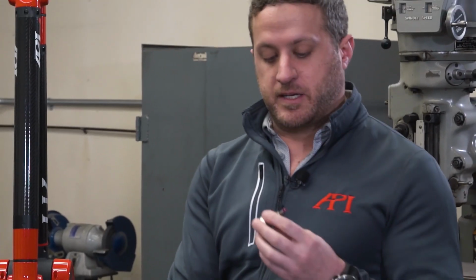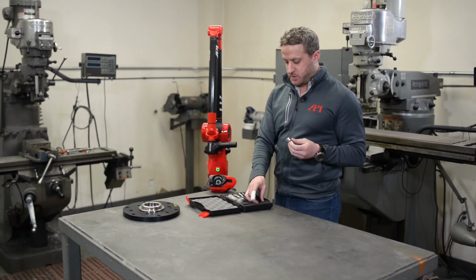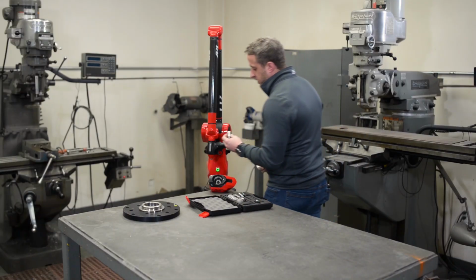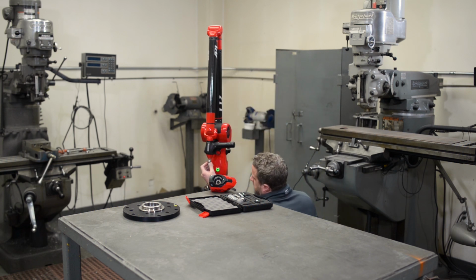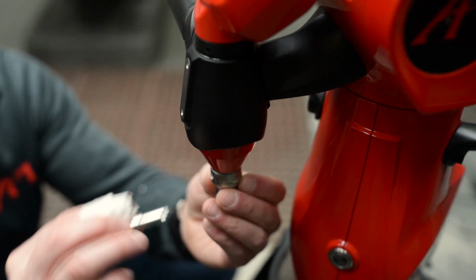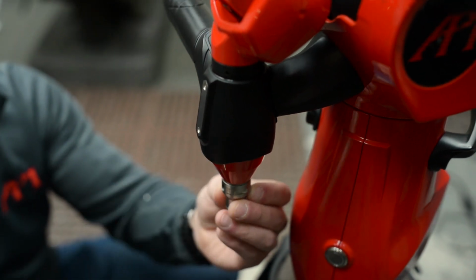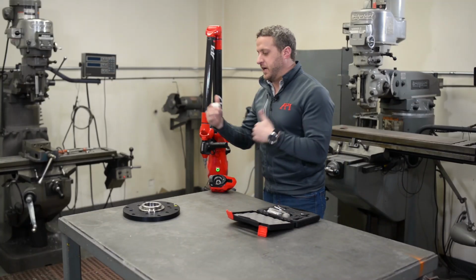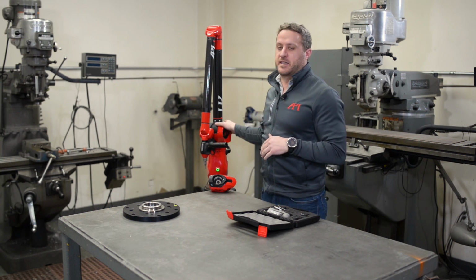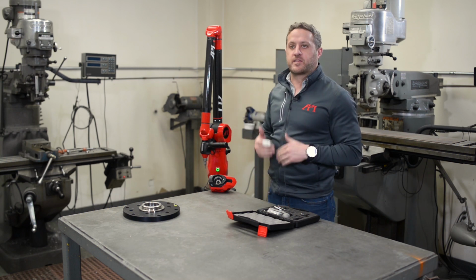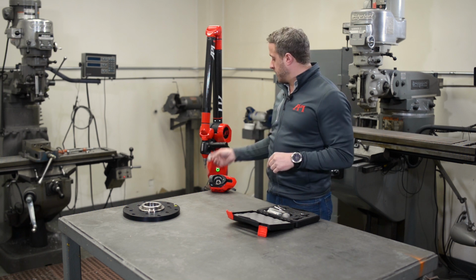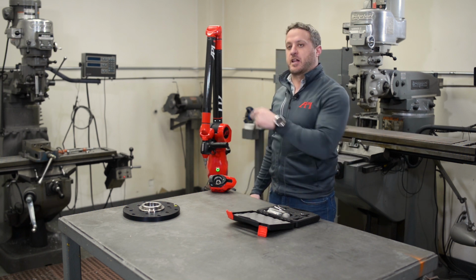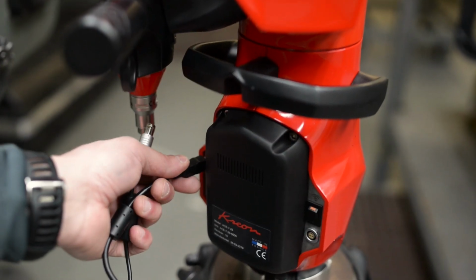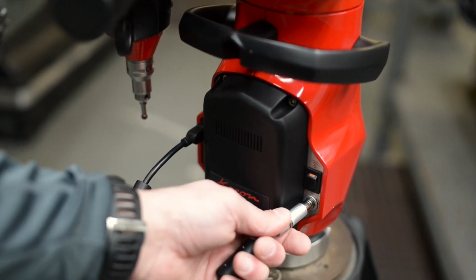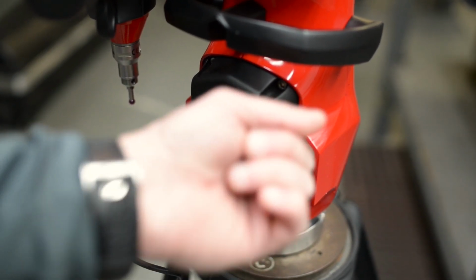So now I'm going to demonstrate installing the probe onto the arm and then going through a calibration process. There is a key inside the toolkit, and what we're going to do is index the probe tip onto the arm, and then use the key to lock it on. Next, I'm going to grab my computer, and we're going to go through how to connect to the arm, check diagnostics, see if the arm is ready to be run, and then go through the probe management and calibrate that probe. Okay, so we're going to plug the arm into the computer. We're going to do this via USB.